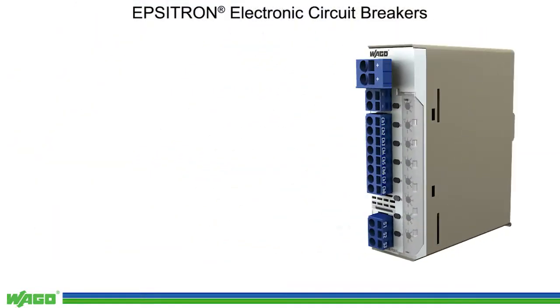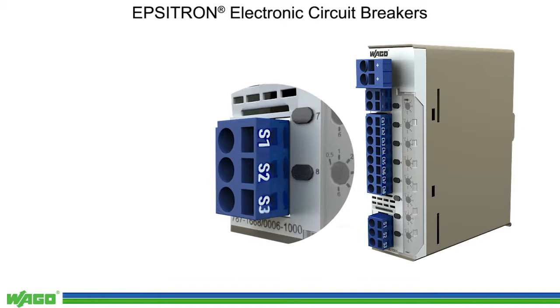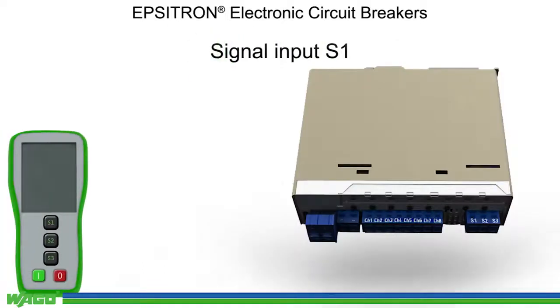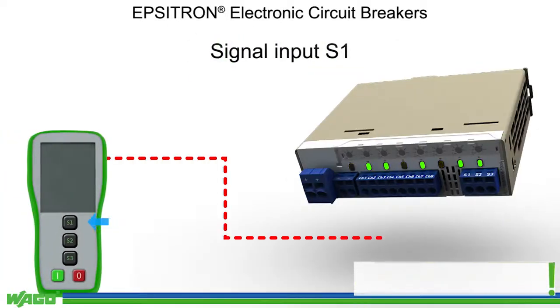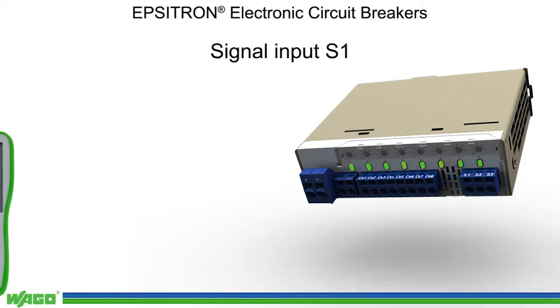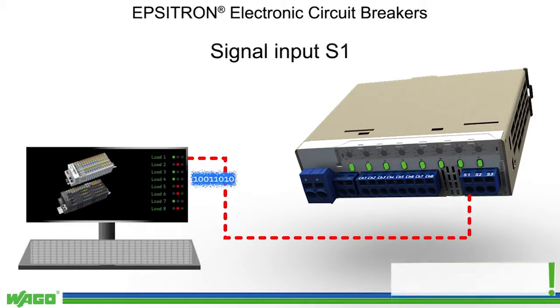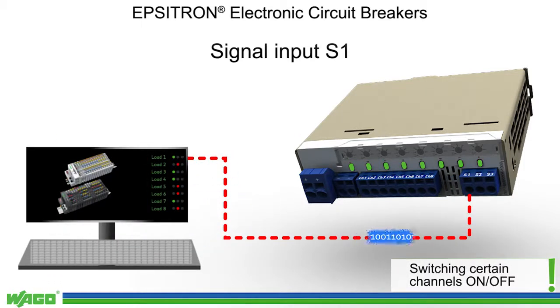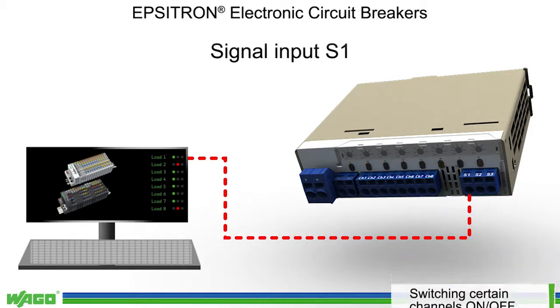WAGO's ECBs feature one digital signal input S1 and two signal outputs S2 and S3 for reading out the operational status. Signal input S1 allows all channels to be remotely reset. In combination with a PLC or an IPC, each channel can be switched on or off separately.